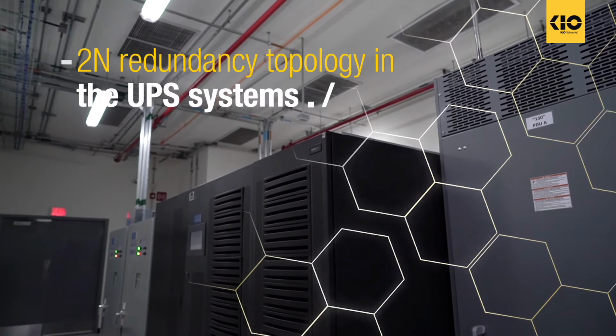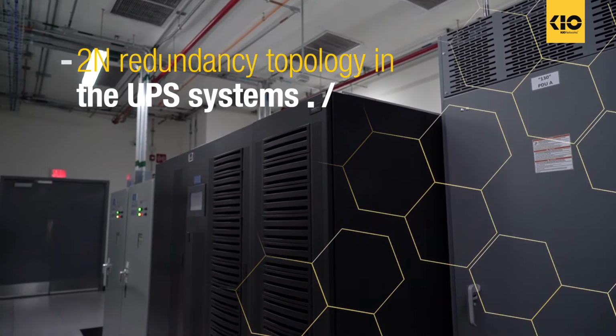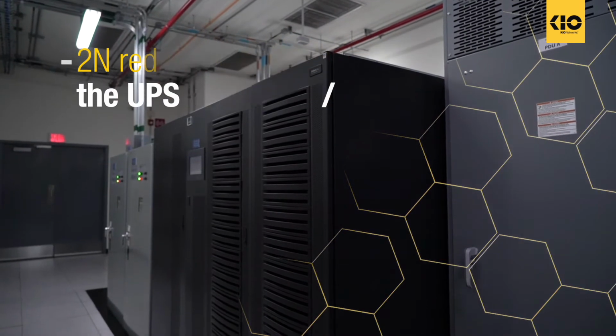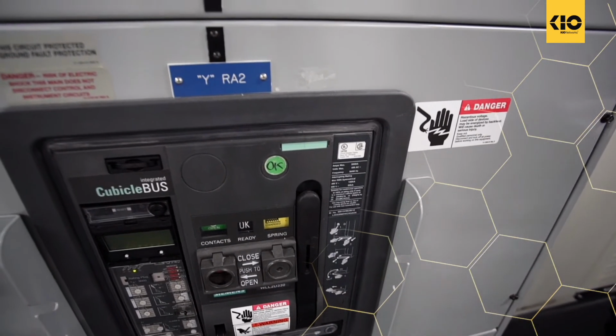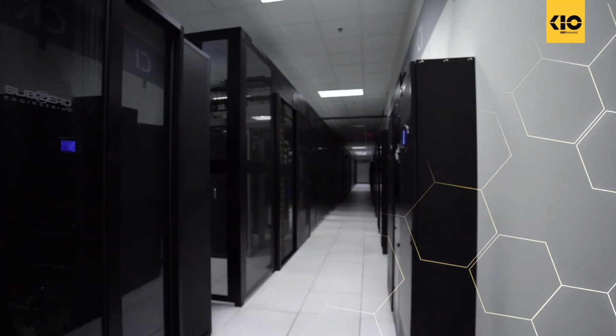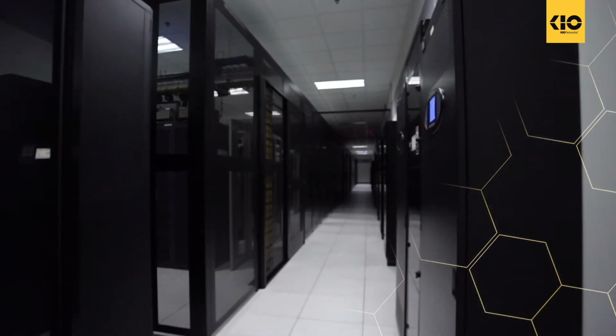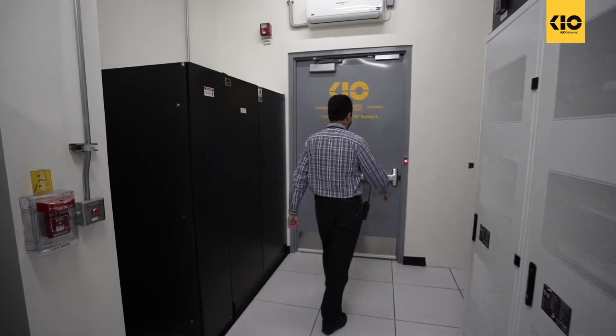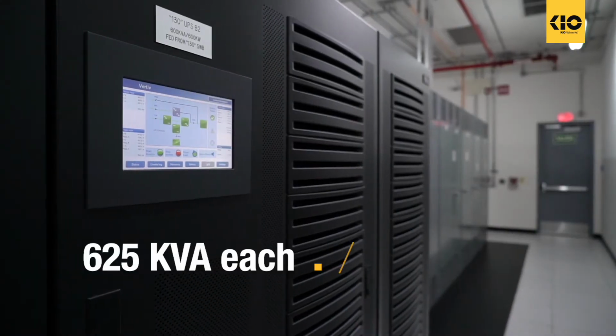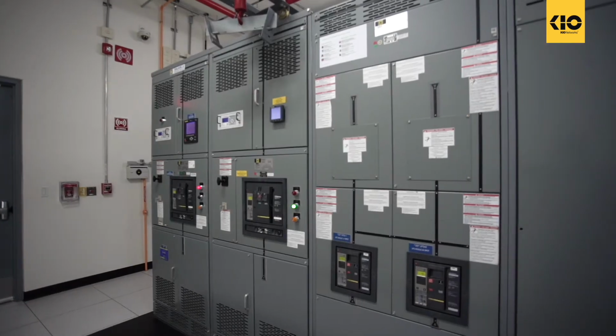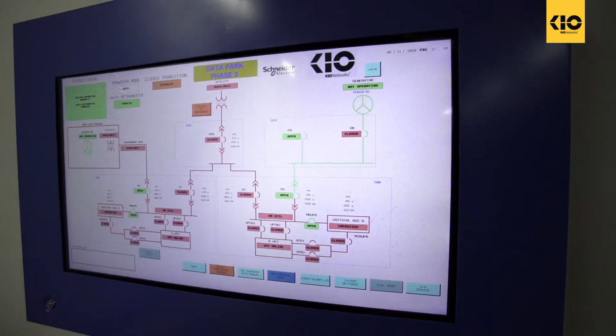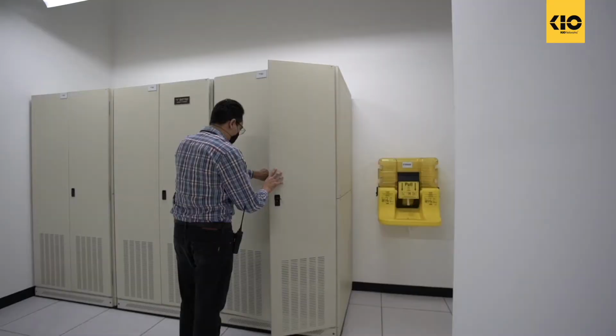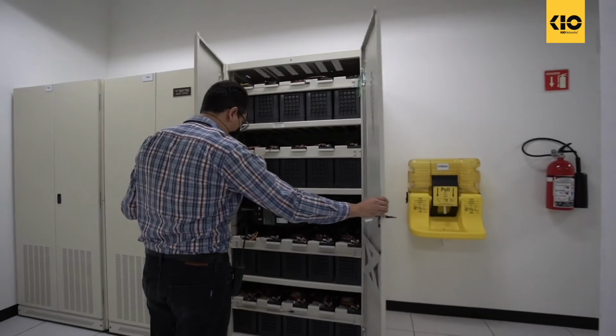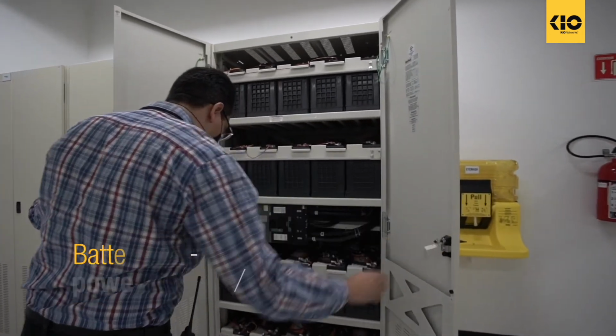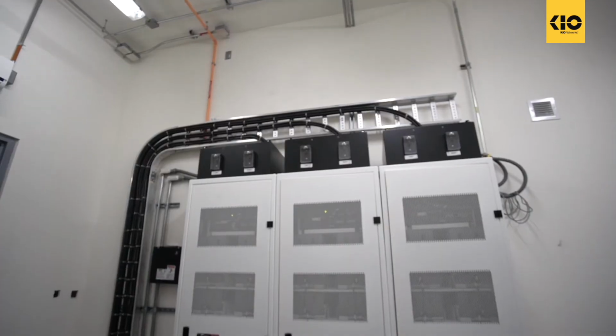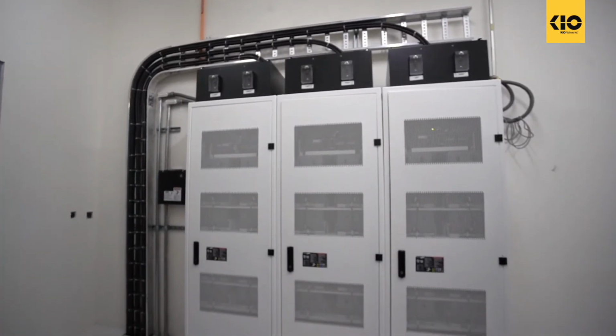We have a 2N redundancy topology in the UPS systems. There are 2 independent UPS systems, one bus A and another bus B, that supply redundant and continuous power to the IT racks. A single UPS system can support the entire load. MEX5 has currently 16 UPS, each with a 625 kVA capacity, and as a compartmentalization measure, it has an exclusive area for UPS and another room for the battery banks. Battery banks have VRLA and lithium-ion batteries that allow the system an autonomy of 7 minutes, even though it only takes 15 seconds to transfer the loads to our generators.